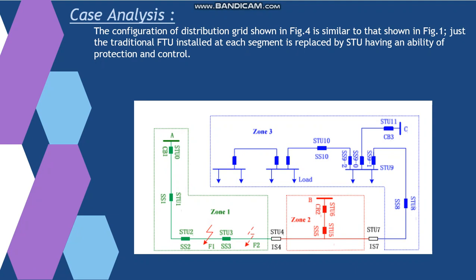STU2 has seen a fault current but STU3 does not detect the fault current because IS4 is open. Therefore, the section between SS2 and SS3 can be identified as the faulted area. And STU3 and STU2 send trip command to SS2 and SS3.